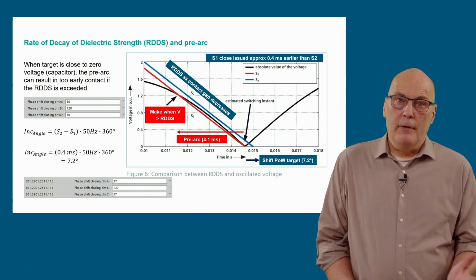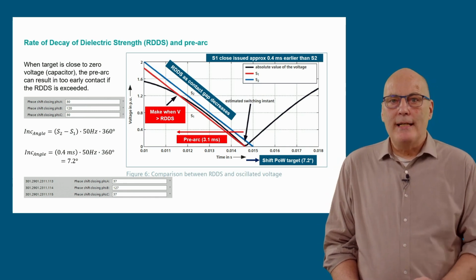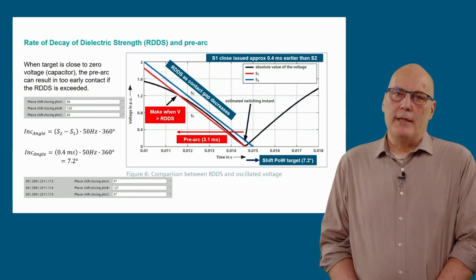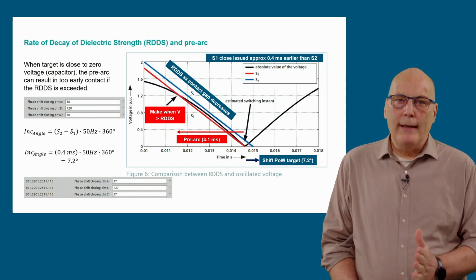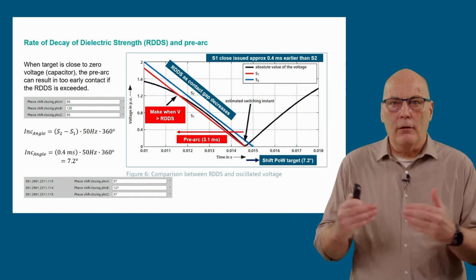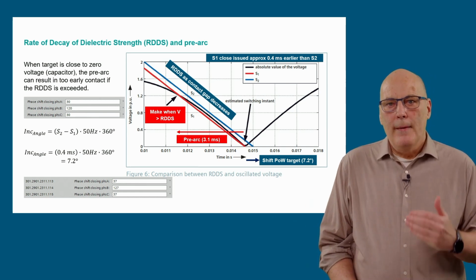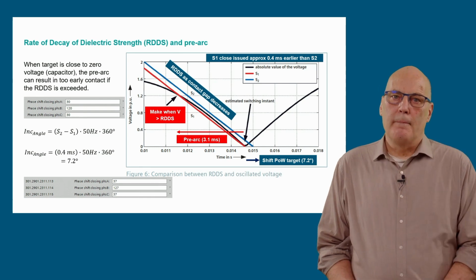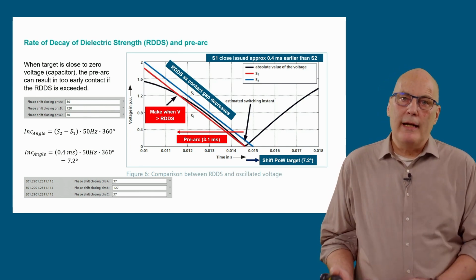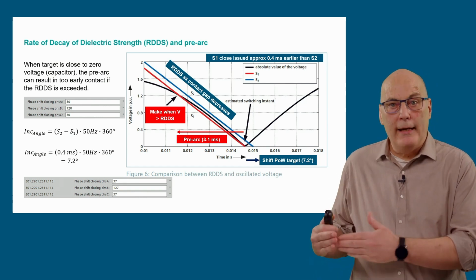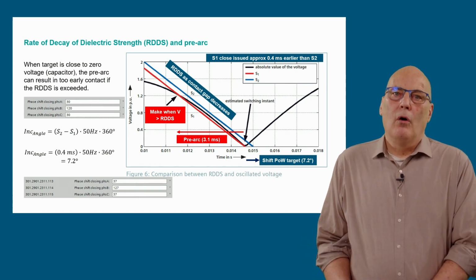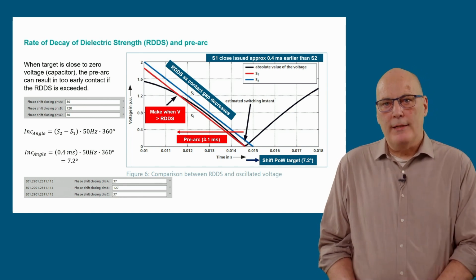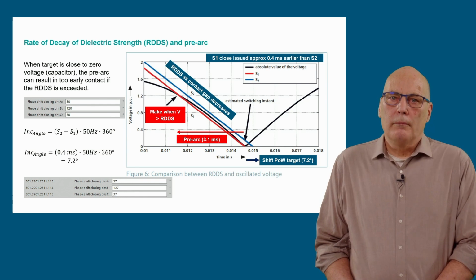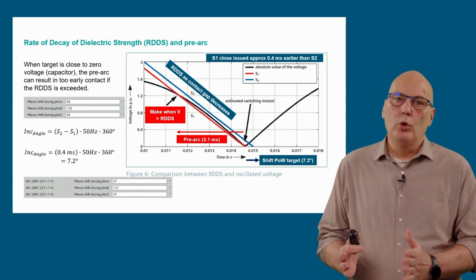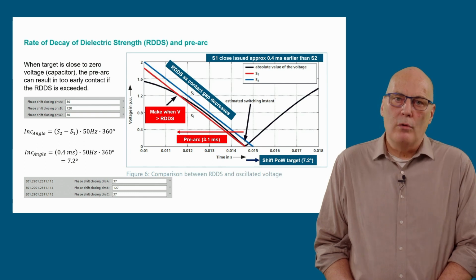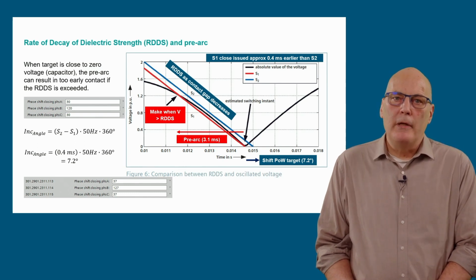With the early closing, red S1 curve, the voltage exceeds the RDDS at 11.5 milliseconds. At this point, electrical contact is made. There's a breakdown and arc comes and current starts flowing. The make time end is determined here. The pre-arc in this case is from 14.6 milliseconds, the intersection or mechanical contact of the S1 curve, where S1 intersects the x-axis, the end of the closing time in other words, and to 11.5 milliseconds where current flow started. That is 3.1 milliseconds pre-arc time.